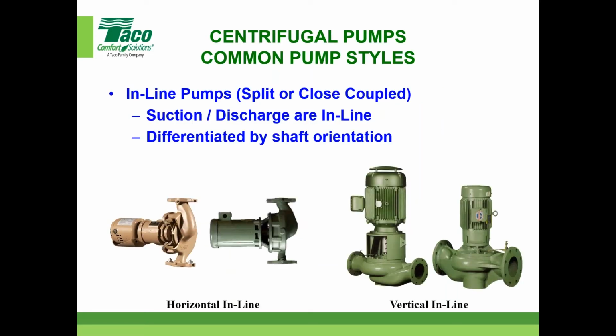Let's talk about different styles of pumps. These are called the inline pumps, split or close coupled, that's kind of common technology or terminology. They're inline because the suction and discharge are inline, even though the motor faces this direction. This is your horizontal, the piping is horizontal, and this is your vertical. Excuse me, it's the motor direction that tells you whether it's a vertical inline or a horizontal inline, so it's differentiated by shaft orientation.